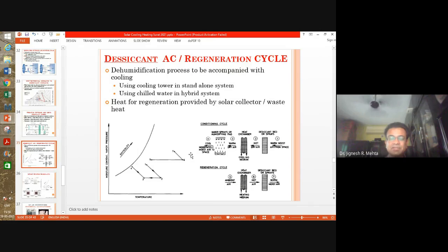This explains the principle of working of desiccant based dehumidification systems. And as you can see, this air gets dehumidified, but then you have to sensibly cool it, and sometimes even evaporative cooling is used as shown here. This is dehumidification, but a temperature rise is there. Sensible cooling is provided. If you're familiar with the psychrometric chart, you can understand it easily. And then this is evaporative cooling for reduction of temperature, right?